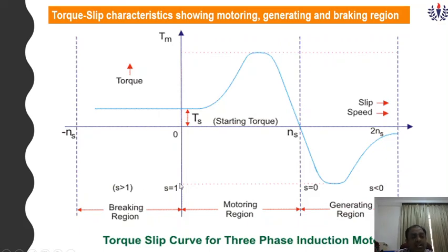So the motor comes to a quick stop under the influence of counter torque, which produces braking action. When the machine runs in the opposite direction, we have to apply the brake so the motor comes to rest. This method by which the motor comes to rest is known as plugging.